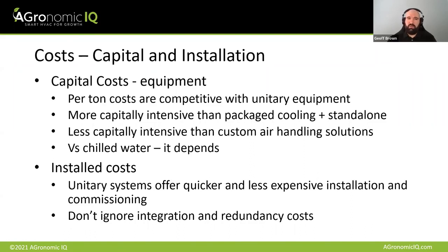The chilled water piece is probably the most challenging piece of this marketplace, particularly as the market continues to legitimize. I've said it before, if you've seen some of my other webinars or seen me speak elsewhere, as the engineering community gets involved in these projects, there is still no guidance from groups like ASHRAE on it. And so in very large projects, the engineering community has tended in the past to focus on what they've done for very large, 1,500 ton, 2,500 ton buildings. And that's historically been central plant. That's how you handle, generally speaking, a large office tower or university campus or big sports center or whatever. And they can be applied successfully to this marketplace, but they're very expensive to do properly. And it's that doing properly piece that's challenging.